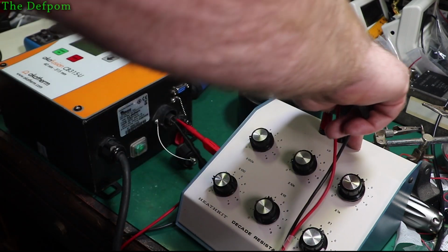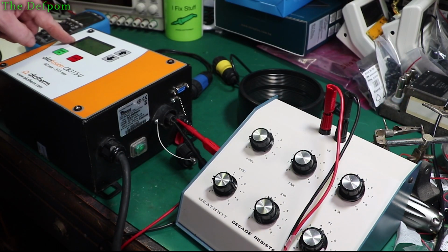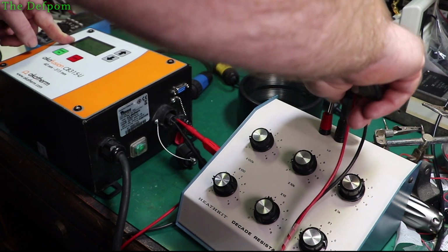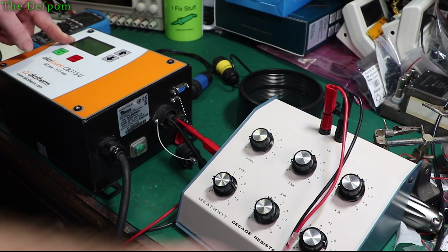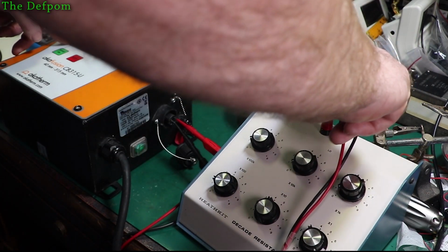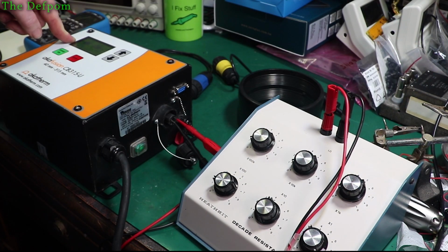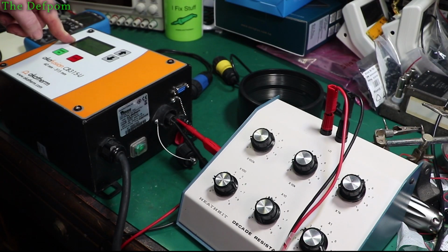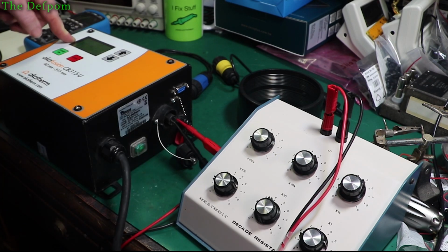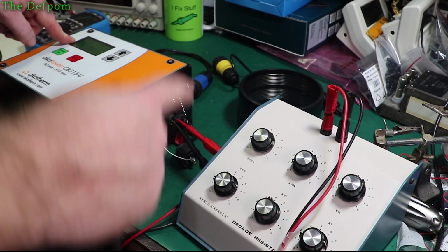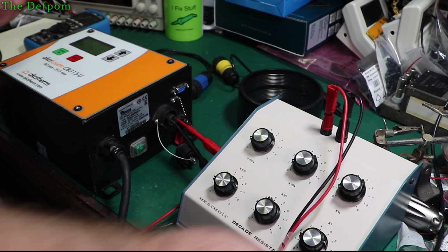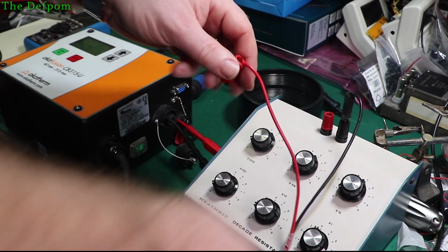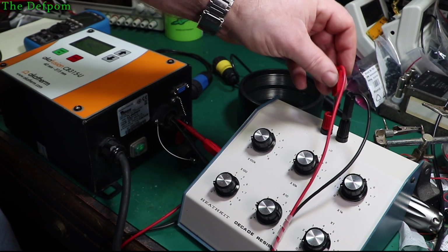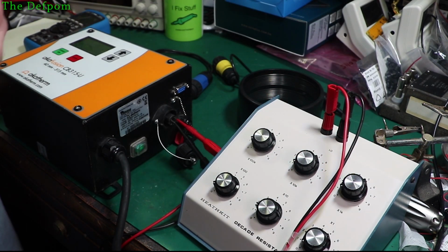So it seems that anything below 140 ohms is going to come up. So if I do say 145 for example, let's see what that does. Still says A00, 147, A00, 149, no, still open, 148, no, 147, yep. So anything below 147 ohms it considers as the A00 assembly. I don't know if it will go to anything else if I do a very different value. So let's do 10 ohms, see what comes up. It says open, detects it as a fault.